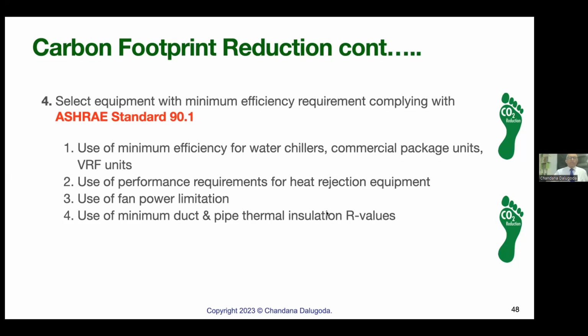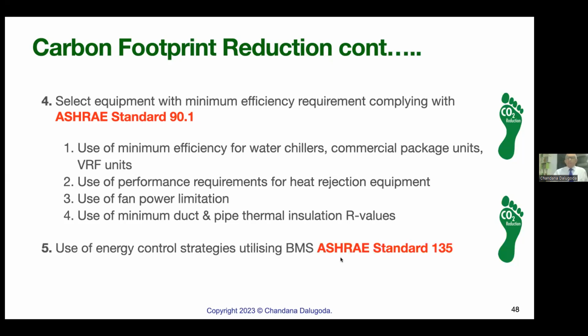Fan power limitation, we'll have to apply to air handling units. We can't, for a given airflow, there's a horsepower limitation. Minimum duct and pipe thermal insulation values, all that has to be verified and complied with. Finally, use of energy control strategies using BMS. Now, what are the strategies? Most of these are coming from the ASHRAE Green Guide.